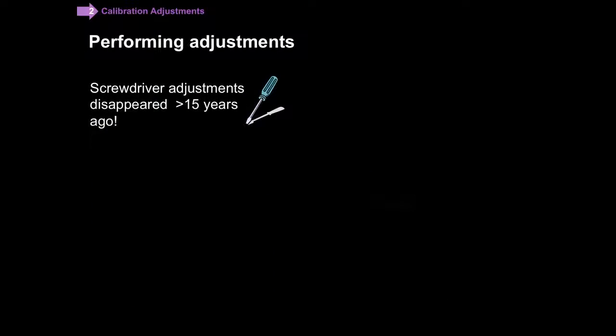Just talking a little bit more about performing adjustments, if you haven't thought about this in a while, you may think that this is you open the cover and make some adjustments with some sort of a hand tool. Screwdriver adjustments have essentially disappeared more than 15 years ago in high performance instruments.